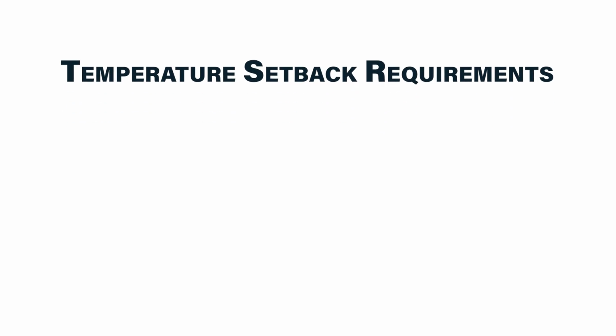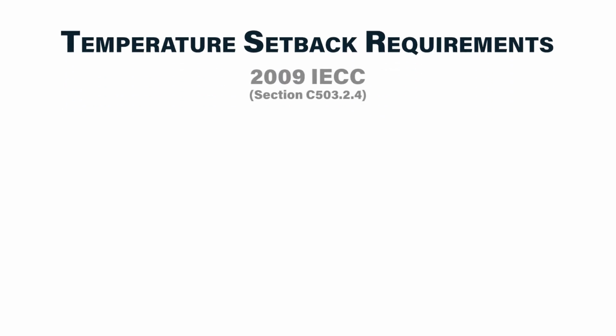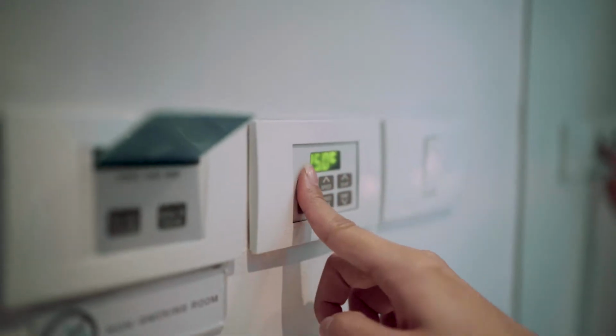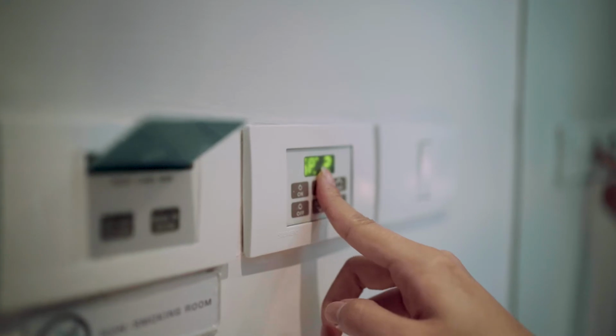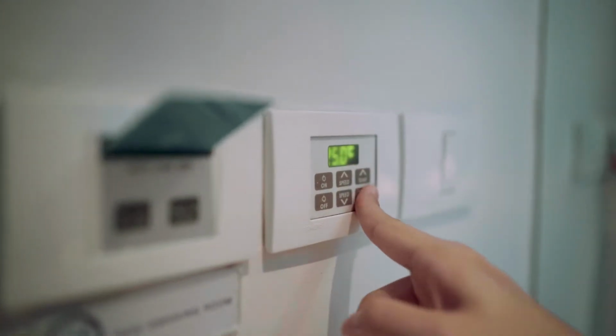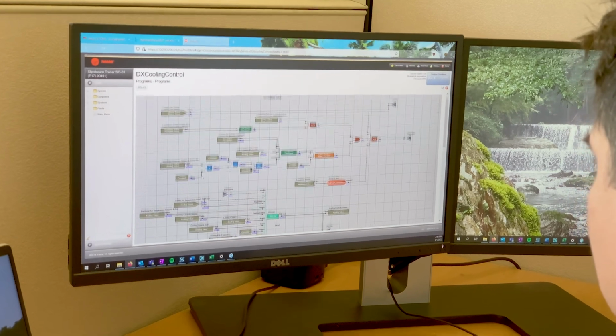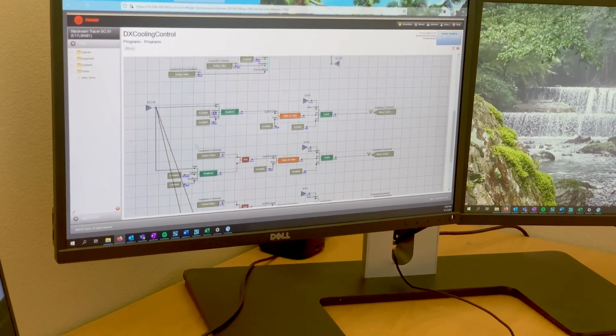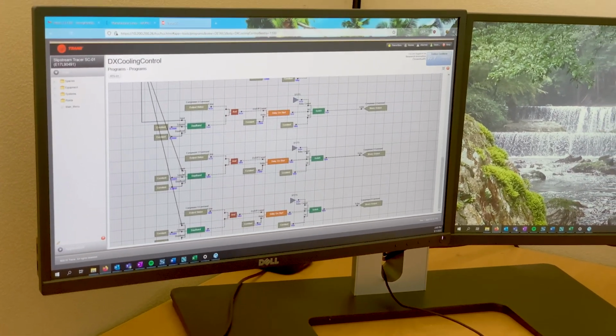The next code update I want to go over is temperature setback requirements. The 2009 IECC required a 5-degree deadband on space thermostats. This means that for the 2.5 degrees above and below set point, the system won't make any changes to correct for space temperature. A smaller deadband would result in the system turning on and off a lot more often to try to maintain set point.